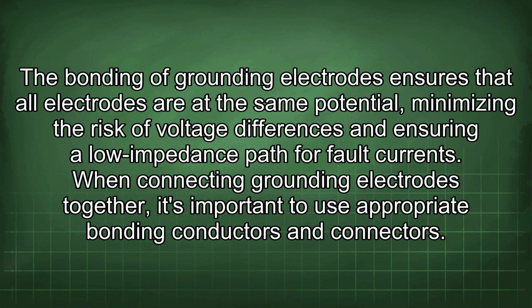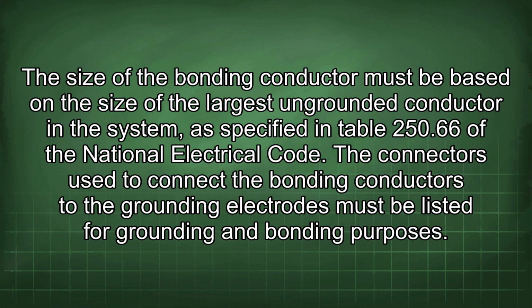When connecting grounding electrodes together, it's important to use appropriate bonding conductors and connectors. The size of the bonding conductor must be based on the size of the largest ungrounded conductor in the system, as specified in Table 250.66 of the National Electrical Code. The connectors used to connect the bonding conductors to the grounding electrodes must be listed for grounding and bonding purposes.